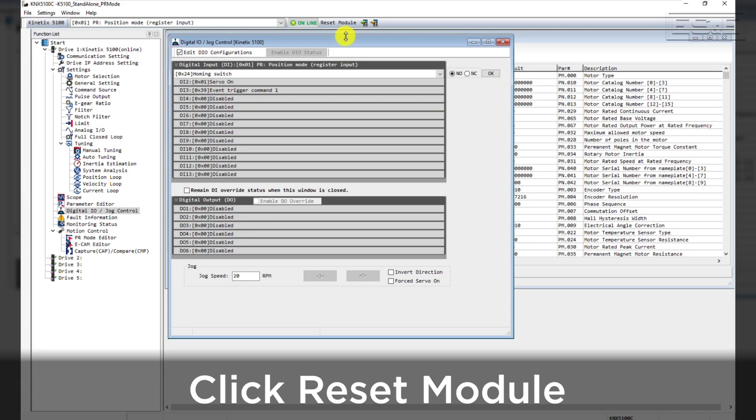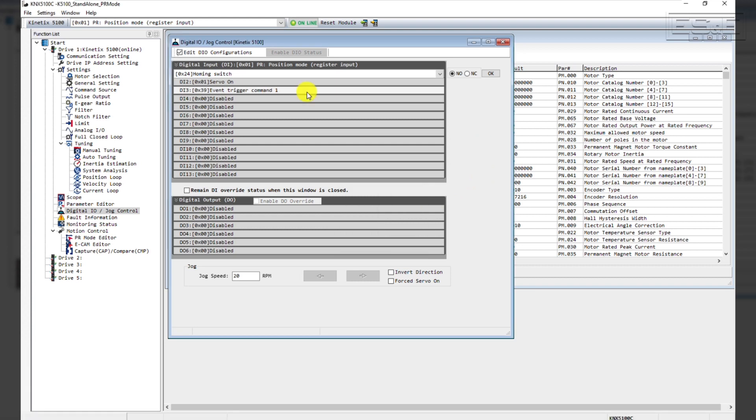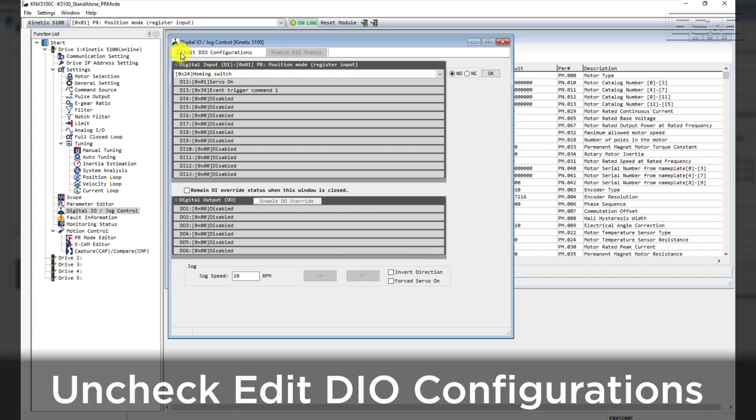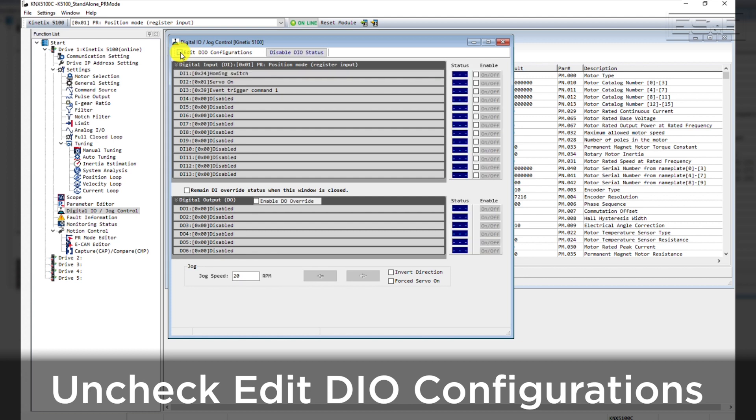Anytime you make a change to the drive, you must reset the drive for the change to take effect. You can click the Reset button at the top of the screen and then click Yes to the prompt to reset the drive. After you're done editing the DigitalIO, you must uncheck the Edit DIO Configurations checkbox.